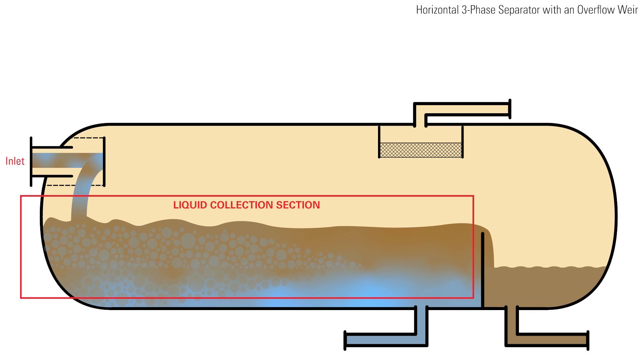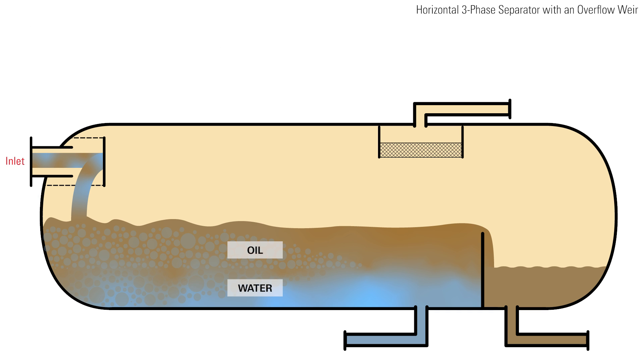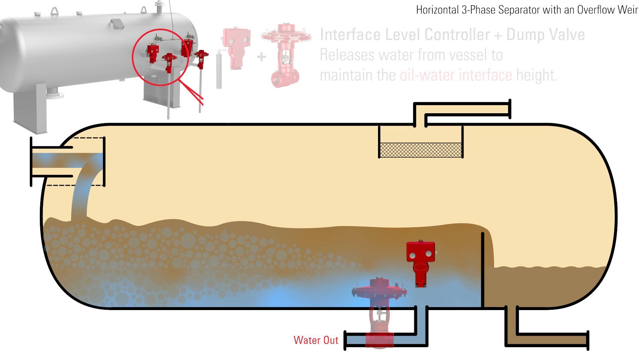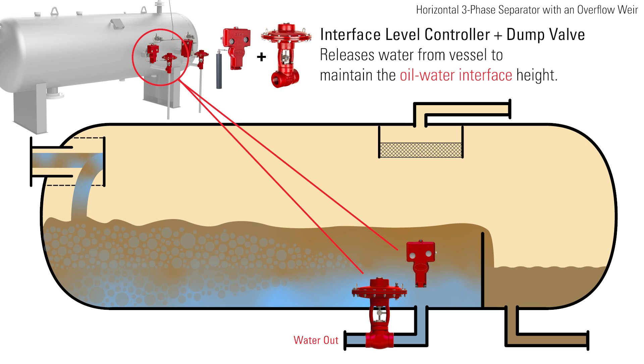In the liquid collection section of the vessel, the oil separates and forms a layer above the water. An interface level controller maintains the oil-water level, signaling a dump valve to release water from the vessel as needed to maintain the oil-water interface height.